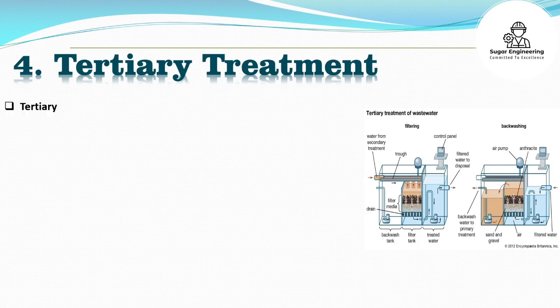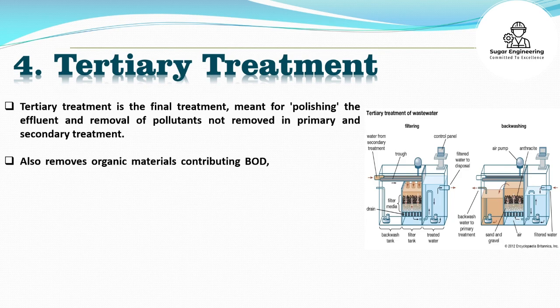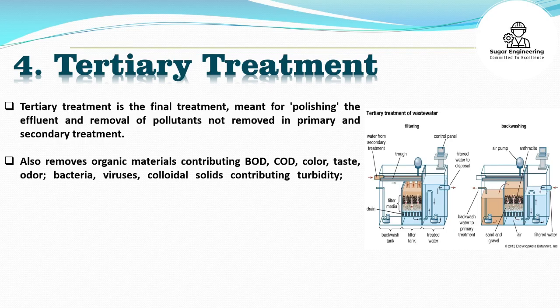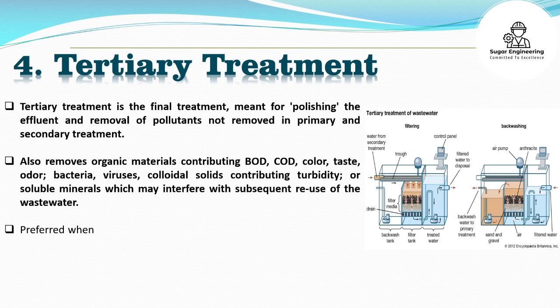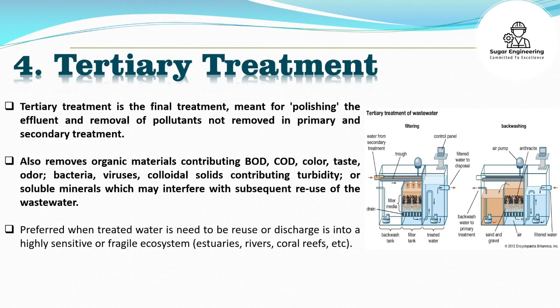Tertiary treatment is the final treatment, meant for polishing the effluent and removal of pollutants not removed in primary and secondary treatment. It also removes organic materials contributing BOD, COD, color, taste, odor, bacteria, viruses, colloidal solids contributing turbidity, or soluble minerals which may interfere with subsequent reuse of the wastewater. It is preferred when treated water needs to be reused or discharged into a highly sensitive or fragile ecosystem such as estuaries, rivers, or coral reefs.